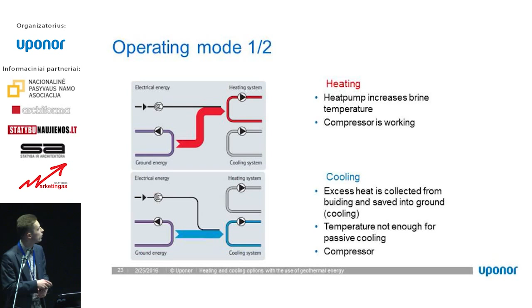And if it's like fan coils, you cannot use passive cooling, you have to use active cooling. This is not very efficient, but we can do it like that. The most efficient way is passive cooling, where we only use electricity for the pumps to circulate water in the primary circuit in the ground, and in the secondary circuit, in the building.